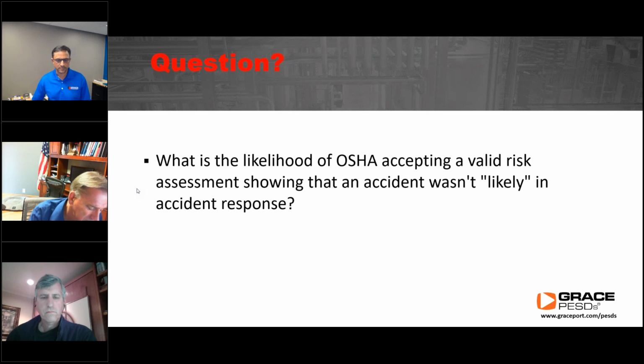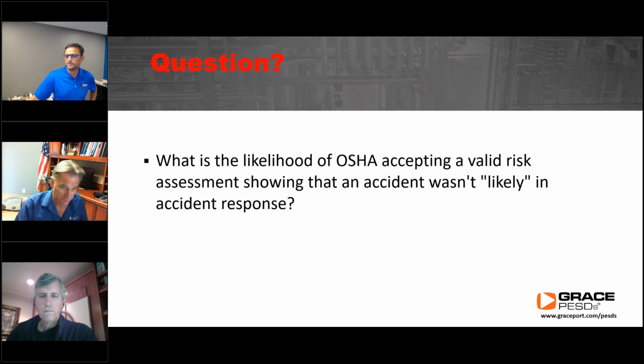So if we've gone through that risk assessment, identified that the inherent risk level was not acceptable, applied the hierarchy of risk control methods to achieve a residual risk level that was as low as reasonably practical, and the qualified person exposed to arc flash and shock has applied all those expected risk control methods, with documentation to prove it, then when the incident investigation occurs, the due diligence of the employer has been demonstrated to be adequate.